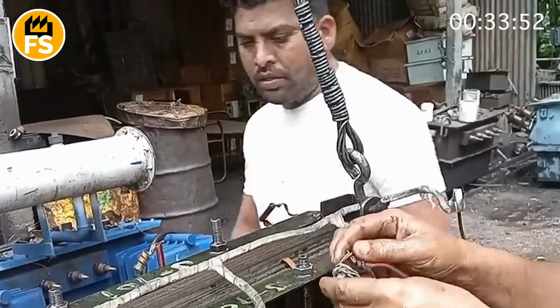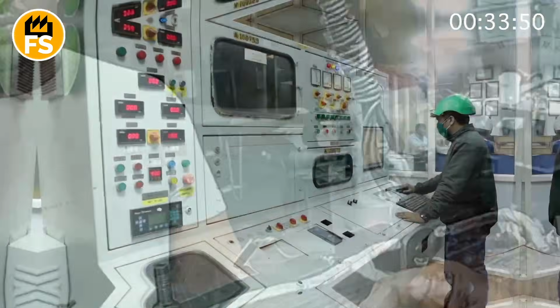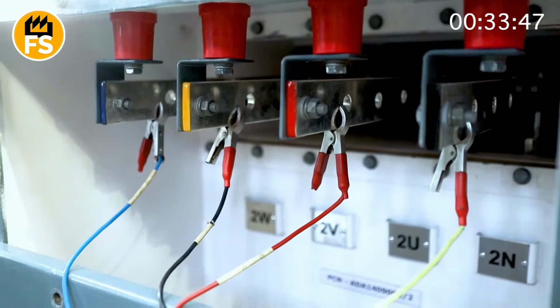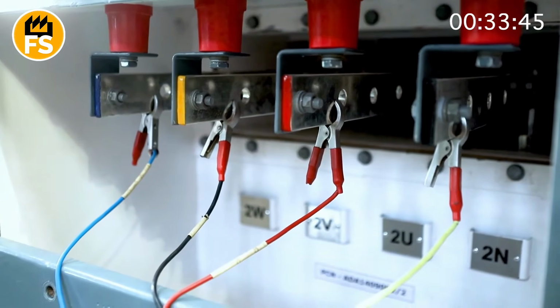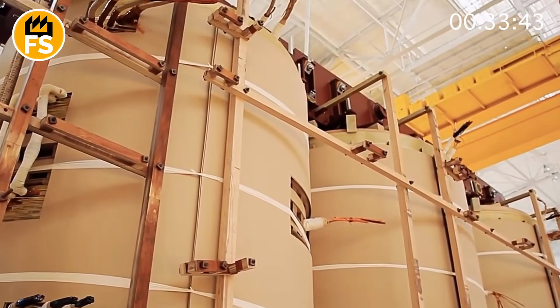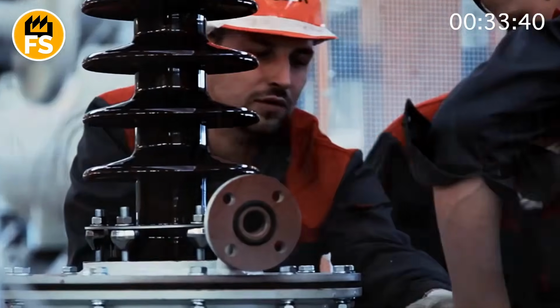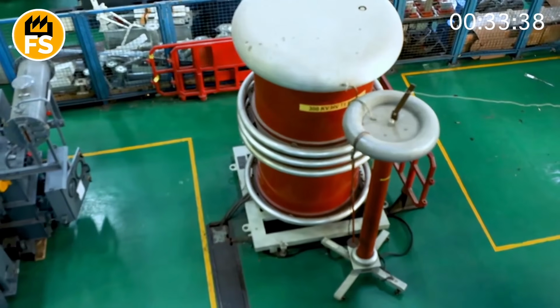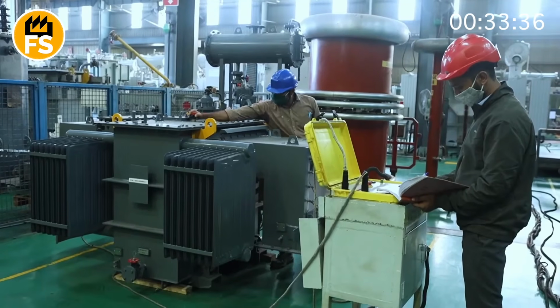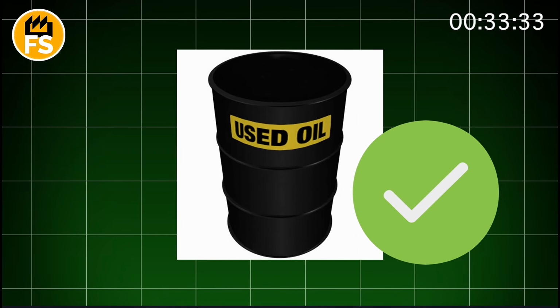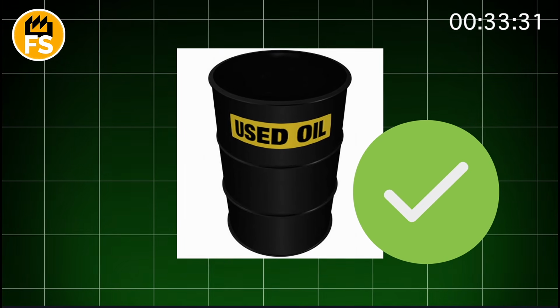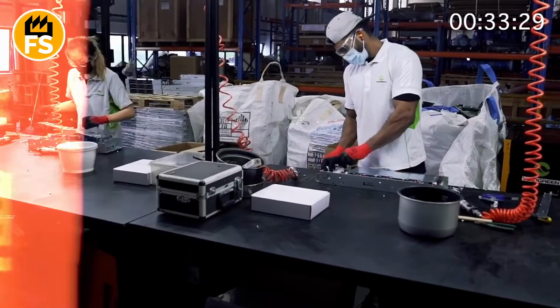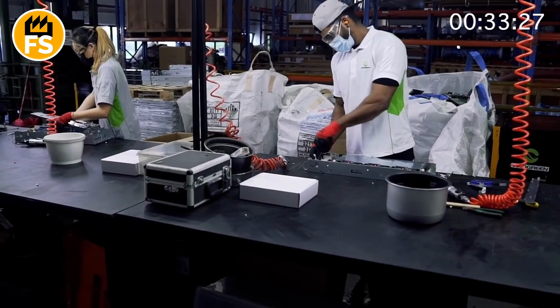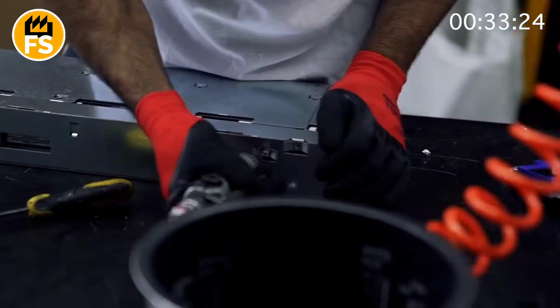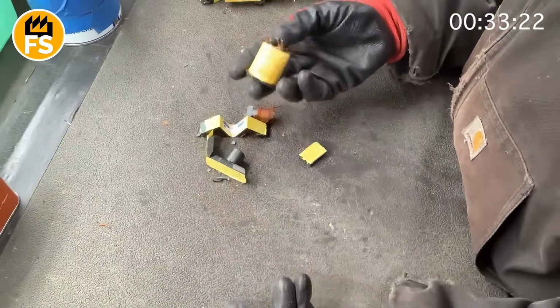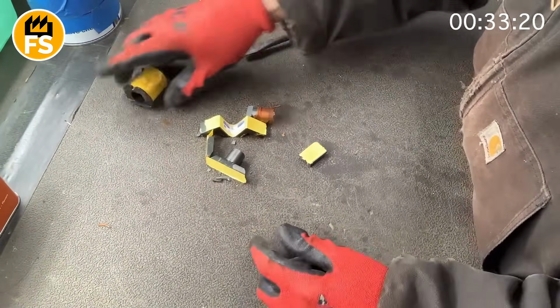Every connection, every hose is checked and rechecked multiple times. This step is the most crucial for protecting the environment from widespread contamination and ensuring the immediate safety of the workers directly interacting with the highly toxic liquid hidden within the steel shell. After every drop of oil is confirmed, safely drained and contained, the transformer must be absolutely de-energized and rigorously verified as safe from any residual electrical voltage.